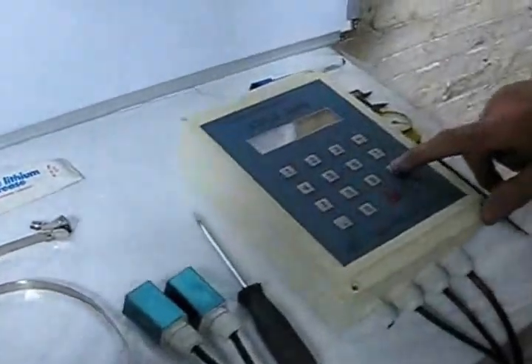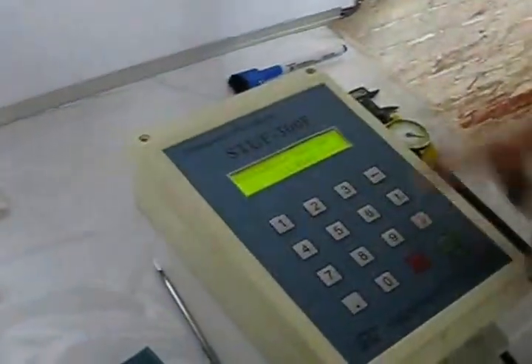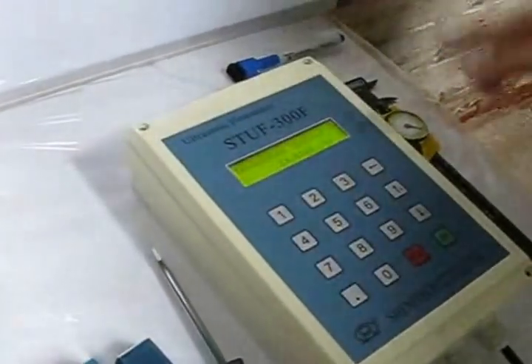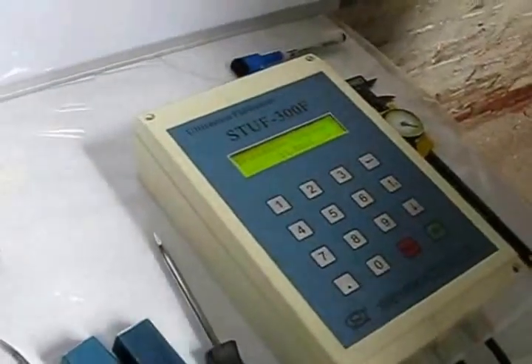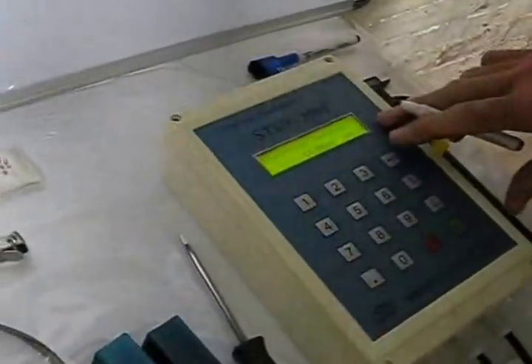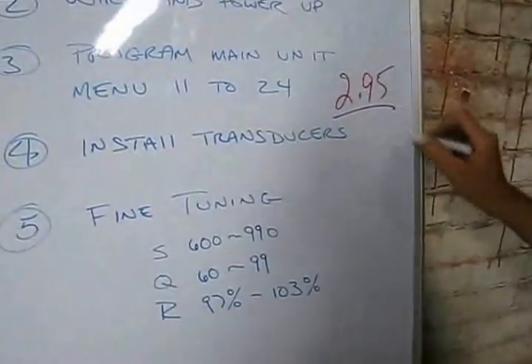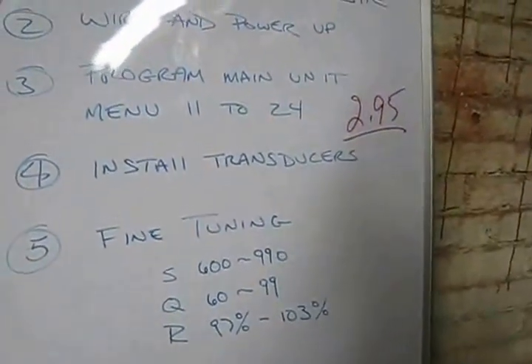The next step is to go to menu 25, which after entering all the parameters of pipe diameter, etc., we will be getting our transducer spacing. The transducer spacing for this type of pipe is 2.95. We need to save this number for the installation of our transducers at a later date.